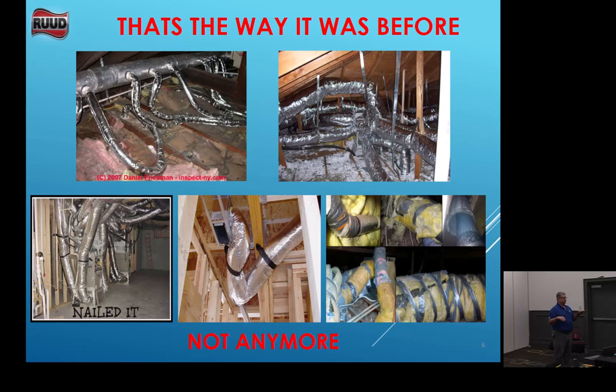Coil temperatures used to be at 40 degrees. Now we're at 45, 48 degree coil temperatures, and they're slowing that air down to get those temperatures down, okay? So we can have some of that latent heat removal. And if we have ductwork out here like this that we just leave in a home, come summertime, with that slower air going across there and that colder temperature air, it's going to rain in the attic, okay?